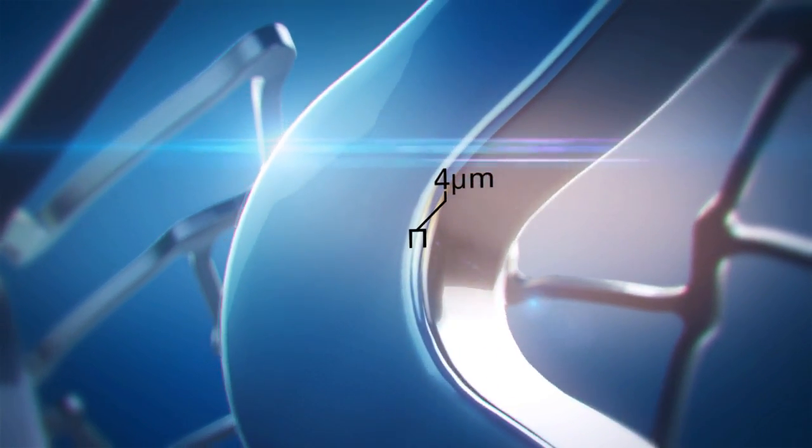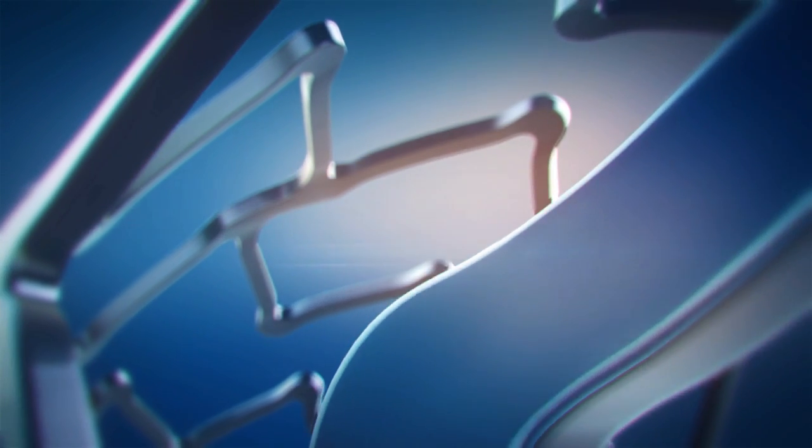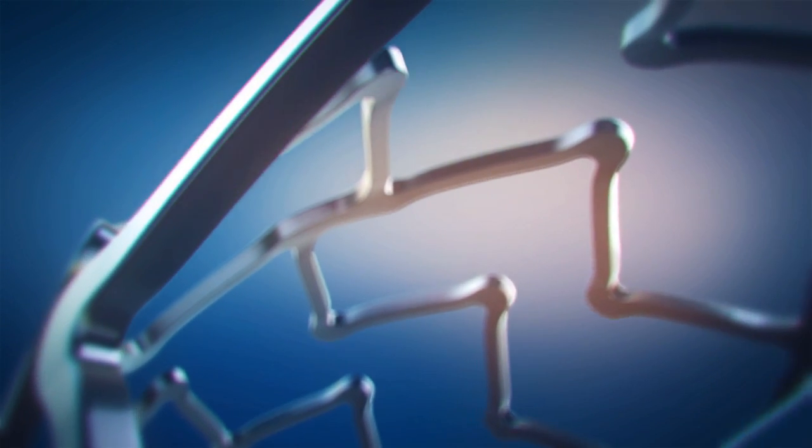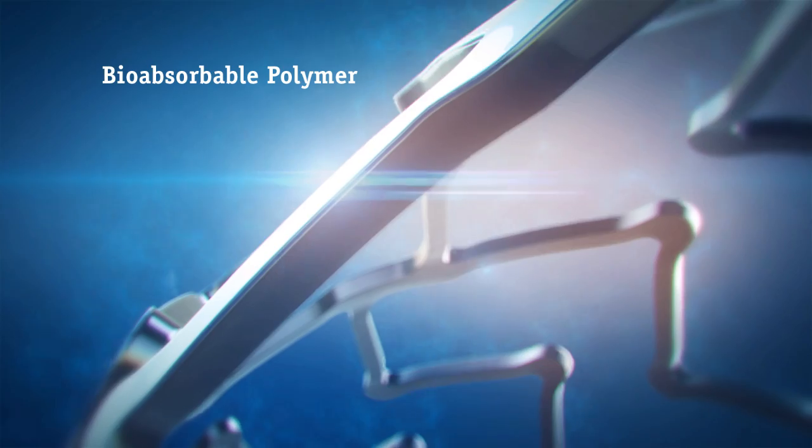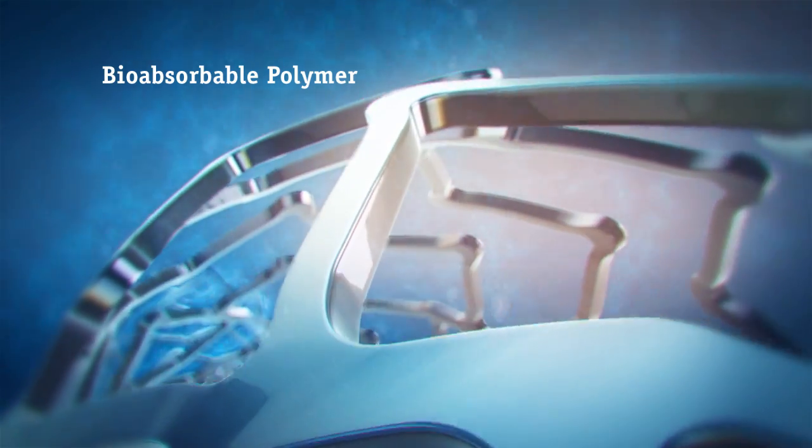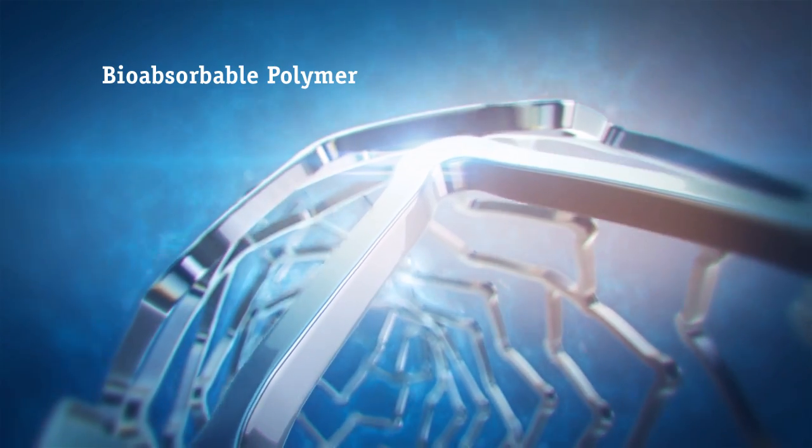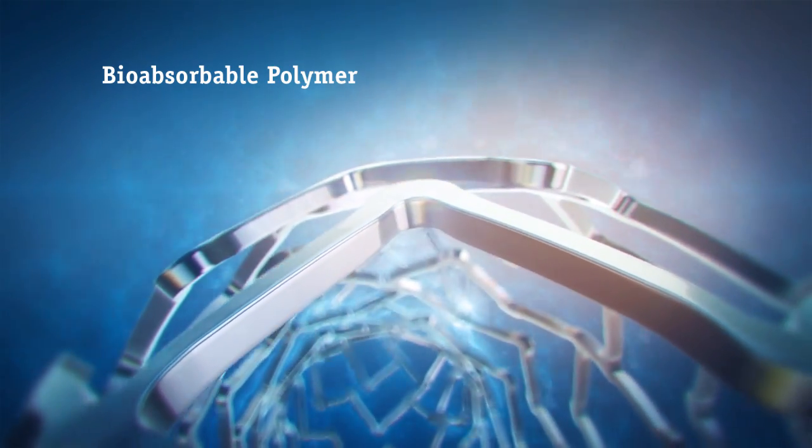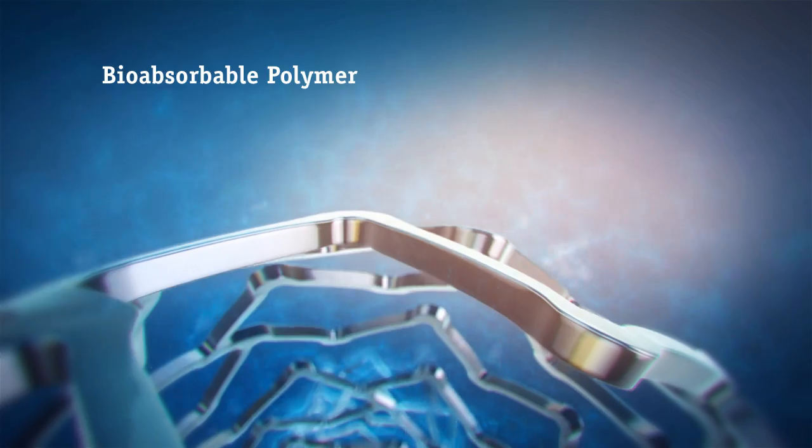The Synergy coating is only 4 microns thick and consists of an amorphic PLGA polymer which allows for faster absorption versus other stents' semi-crystalline bioabsorbable polymers. It is also coupled with market-leading Everolimus drug, allowing for synchronous drug and polymer absorption.